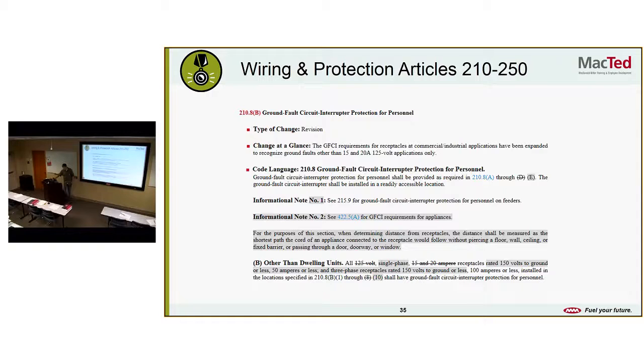Other than dwelling units, looks like they scratched out the 125, the 15, and the 20 amp. So now single phase rated 150 volts to ground or less, 50 amps or less, and 3-phase receptacles rated 150 volts to ground or less, 100 amps or less installed in the locations specified in 210.8 shall have ground fault circuit interrupter protection for personnel. That's a pretty big swath of equipment right there, including 3-phase. So that's a big one. That's a lot of requirements for GFIs.